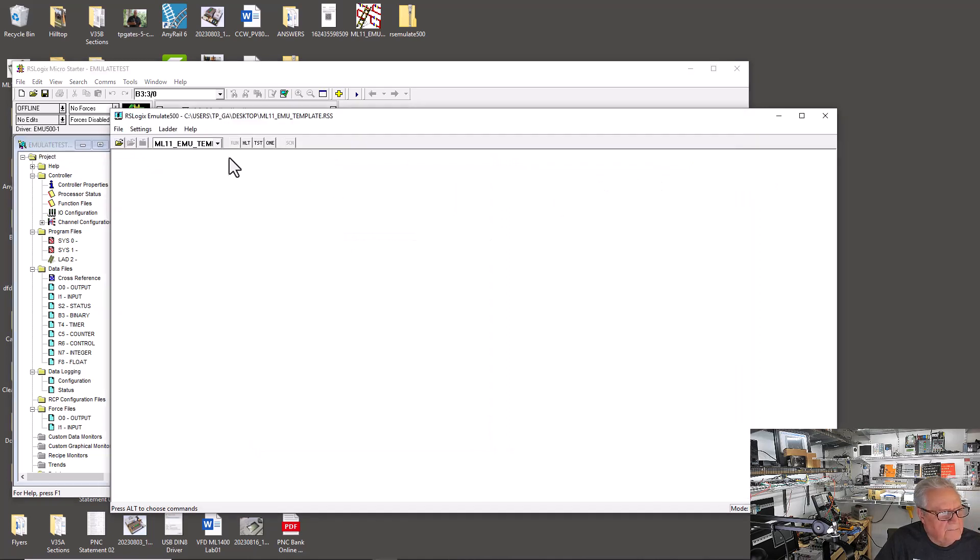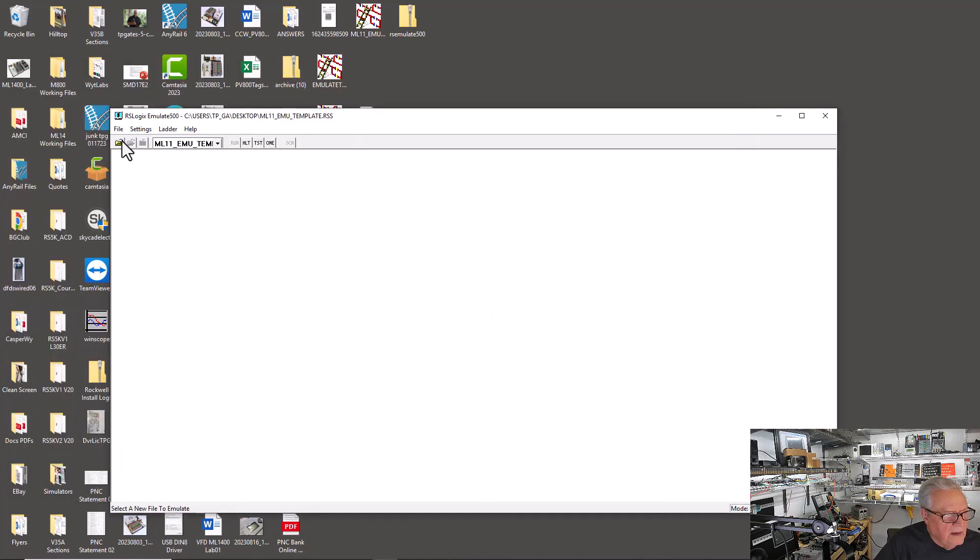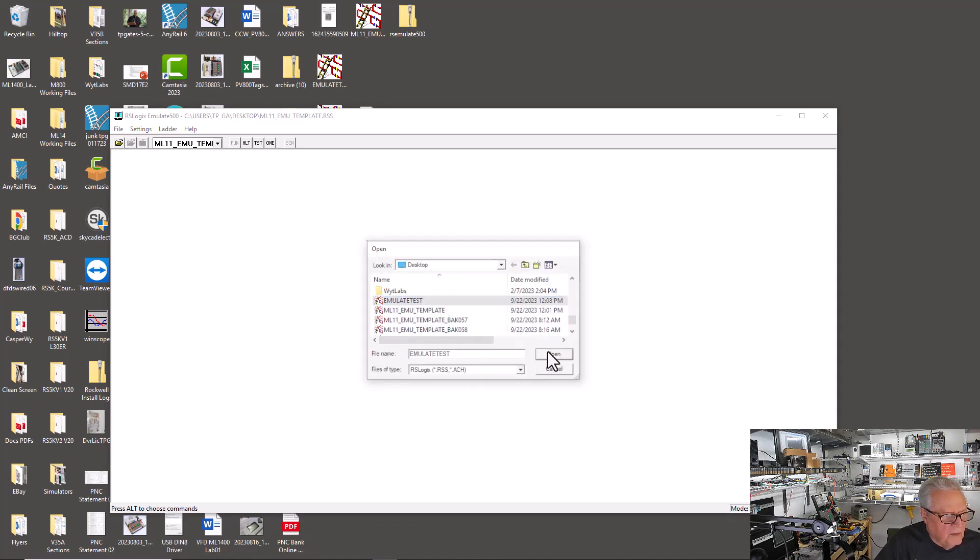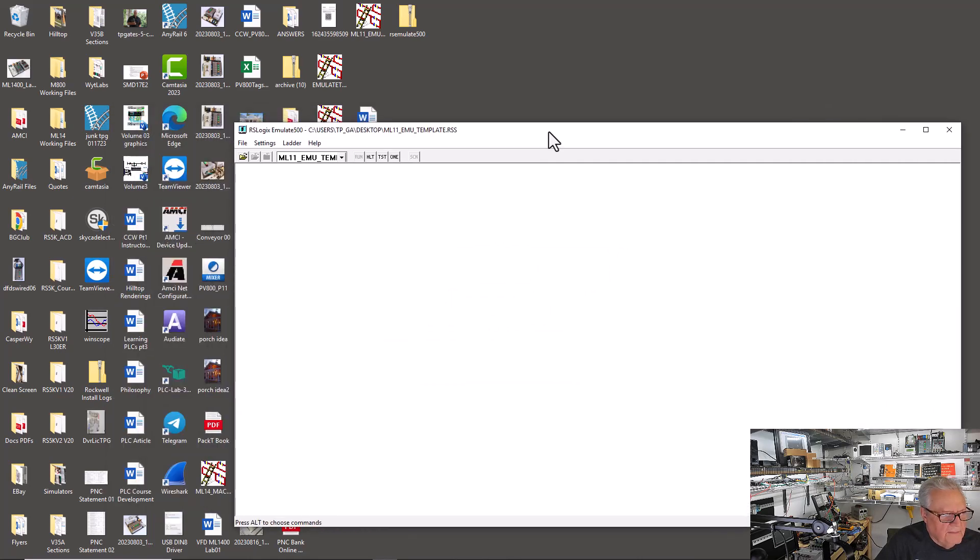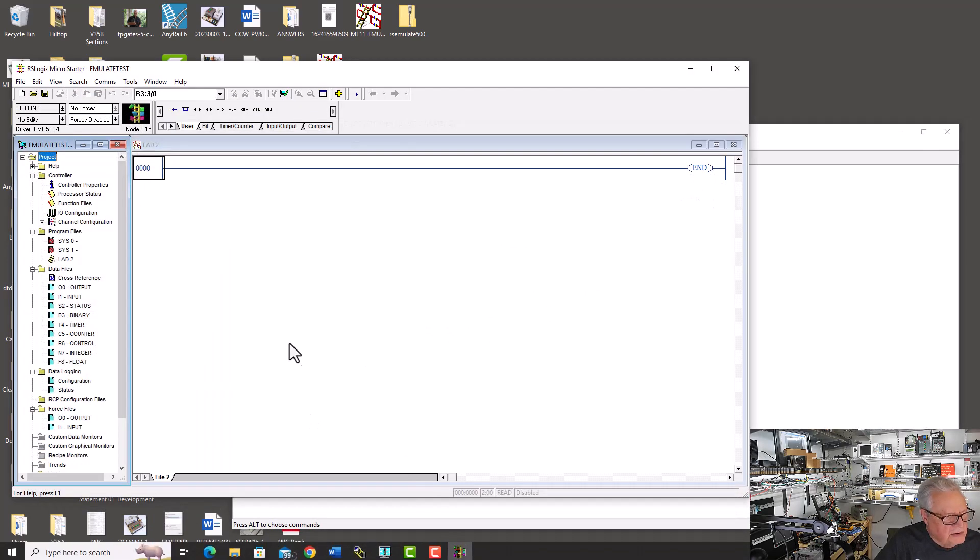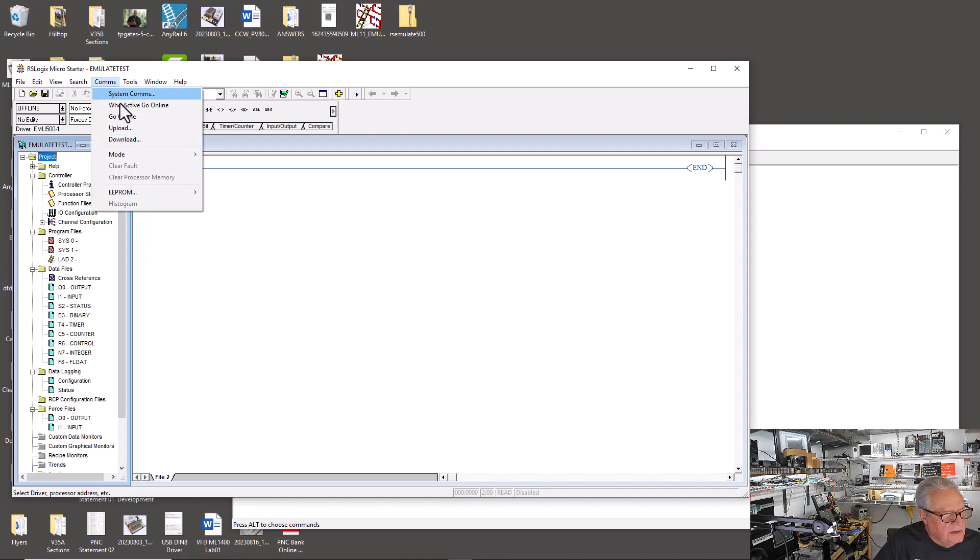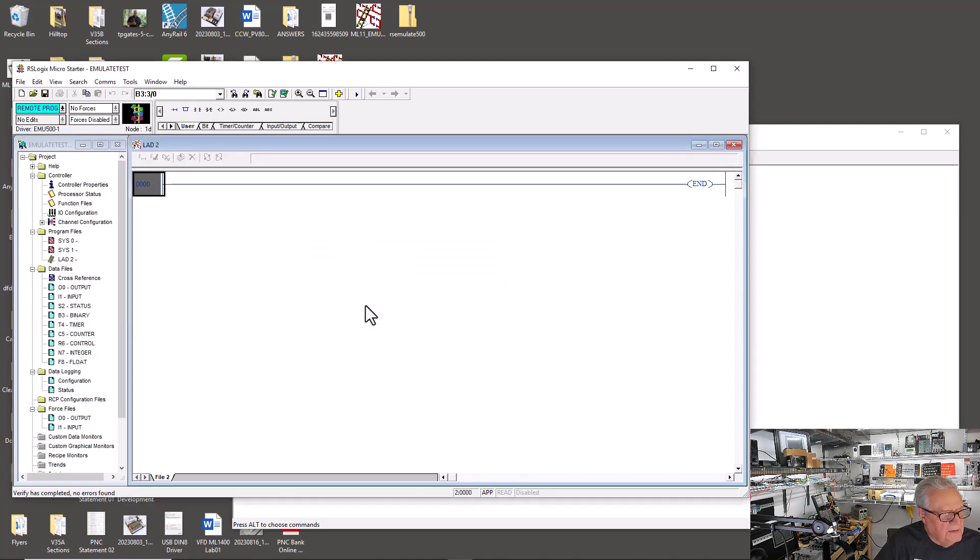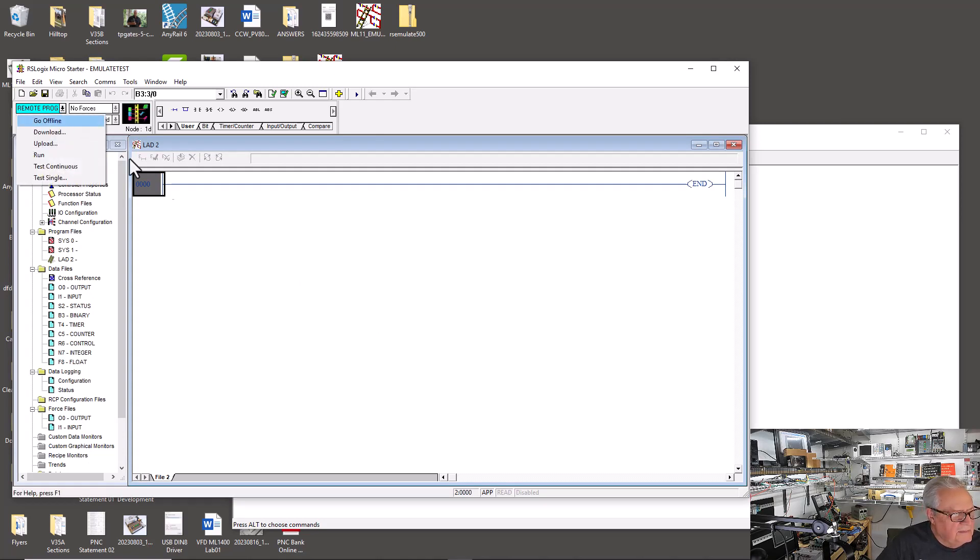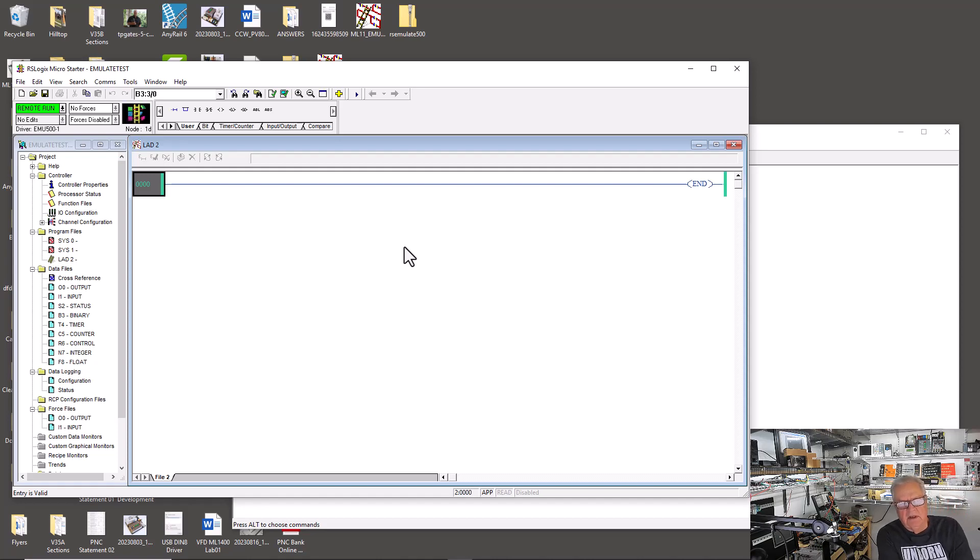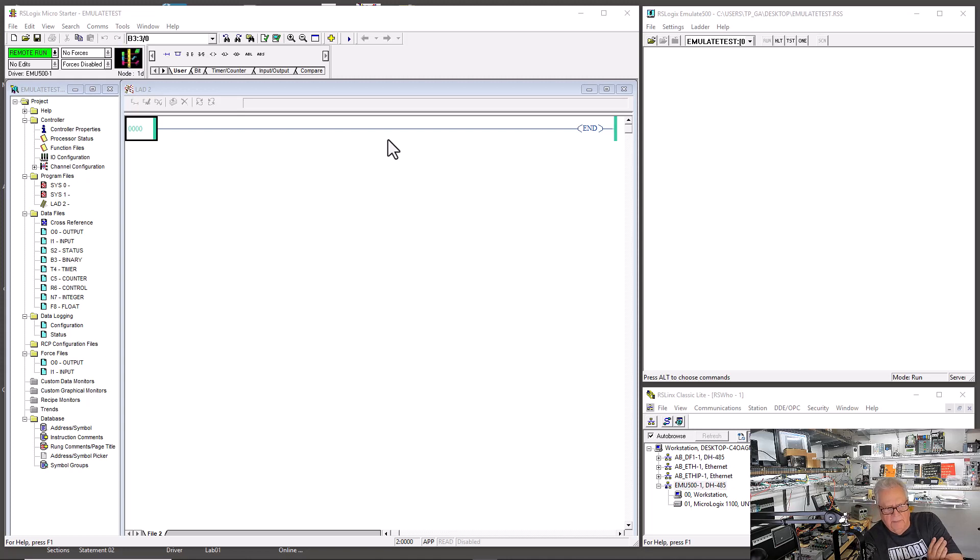Now I'm going to open up the emulator. RS Logix Emulate 500. I would open this up and scroll down to where I saved that project that I had created, untitled, and just save as Emulate Test. I'm going to save it. I'm going to open the file. Go to Desktop, Emulate Test, Open. And I'm going to do a comms. My driver is specified as the emulator driver. I'm just going to click on Download. I just downloaded that project to the emulator. I can put it in the Run Mode. And the emulator does not support online editing.